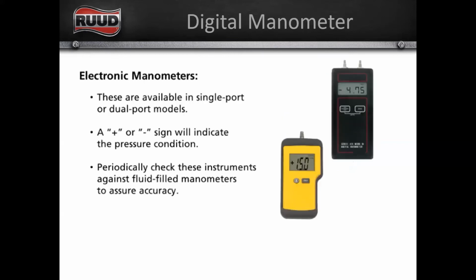Wade, yeah. I got a couple questions, and I think this may explain it right here. One of the questions was, can you have a negative return static pressure? And I've found with some instruments, they'll read that pressure as a negative number, whereas your Dwyer magnehelic reads it as a positive number, even though it's negative pressure. So I think that may be where the confusion's coming in, unless you want to elaborate on that a little more. Yeah. So the return static is always going to be negative because it's on the negative side of your differential.